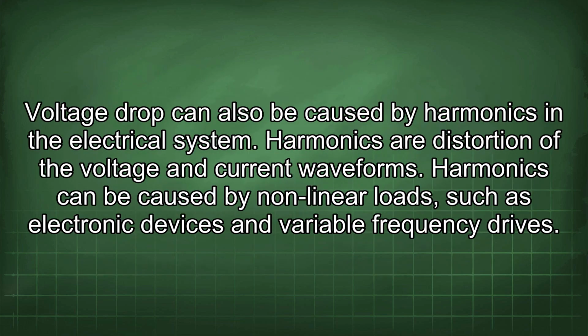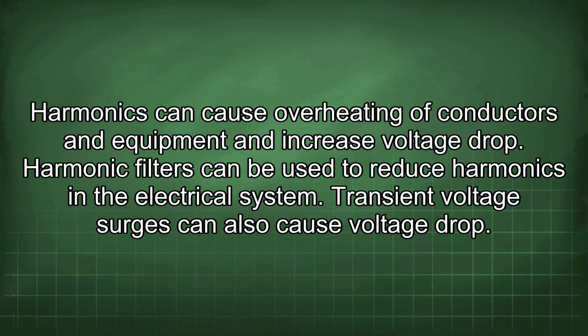Voltage drop can also be caused by harmonics in the electrical system. Harmonics are distortion of the voltage and current waveforms. Harmonics can be caused by nonlinear loads such as electronic devices and variable frequency drives. Harmonics can cause overheating of conductors and equipment and increase voltage drop. Harmonic filters can be used to reduce harmonics in the electrical system.